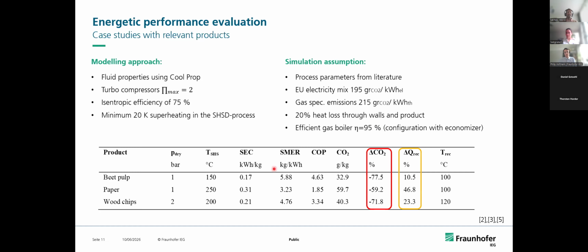Also crucial is the recuperation potential. I mentioned that a fraction of the mass flow can be used outside the system. Why? We bring in new water with the stream of the wet product into the system, and this is mostly converted into steam, which is part of the mass equation. We also use electrical energy for compression of the steam, which is immediately converted into heat. This means that just to fulfill stationary operation of the system, we have to let out some mass and some heat.